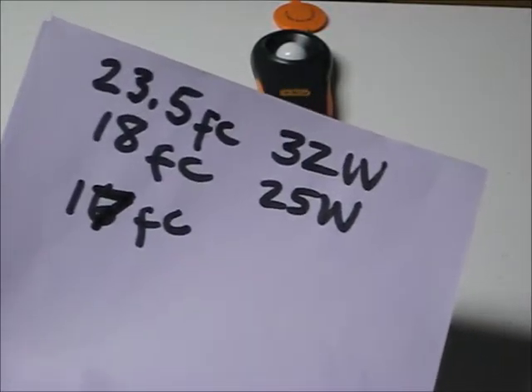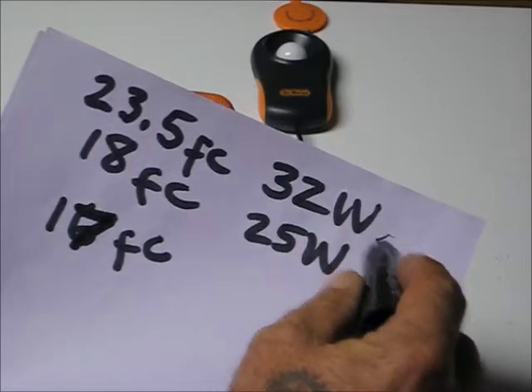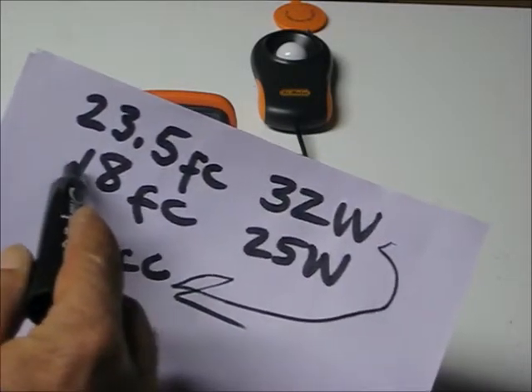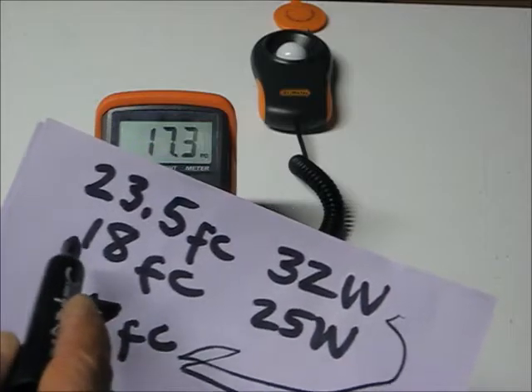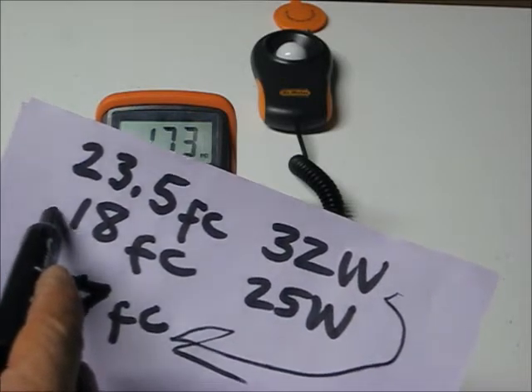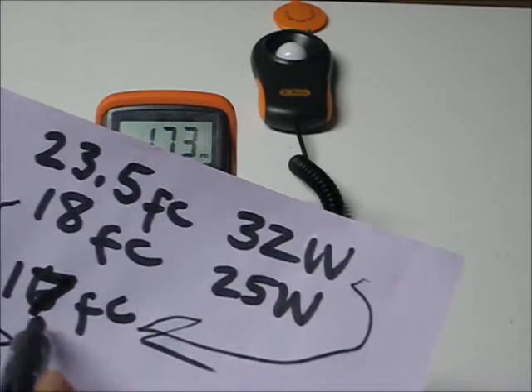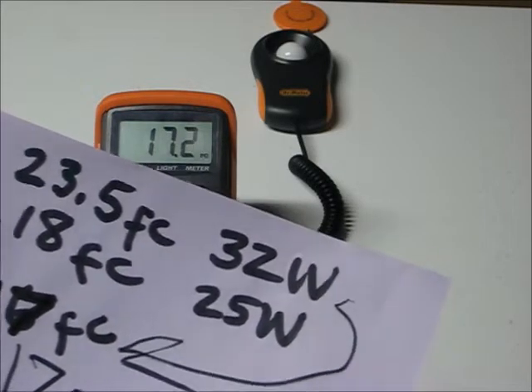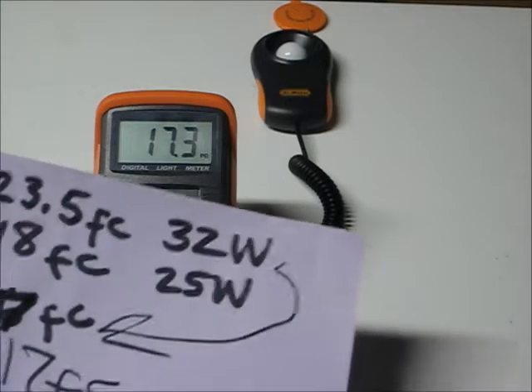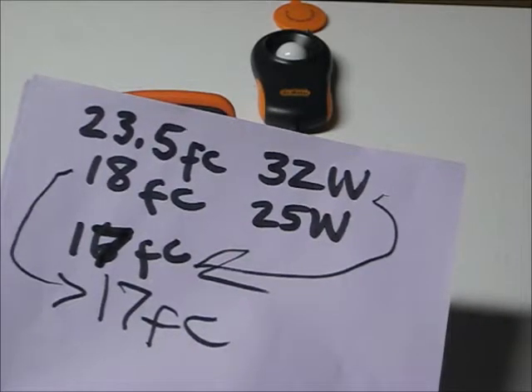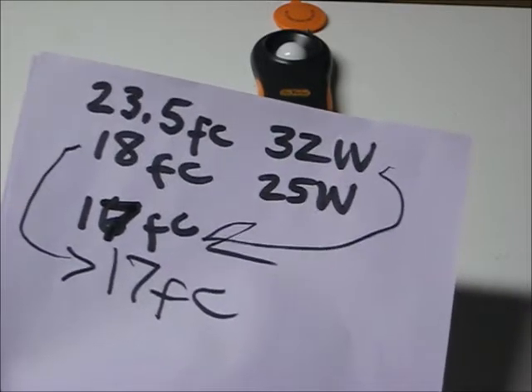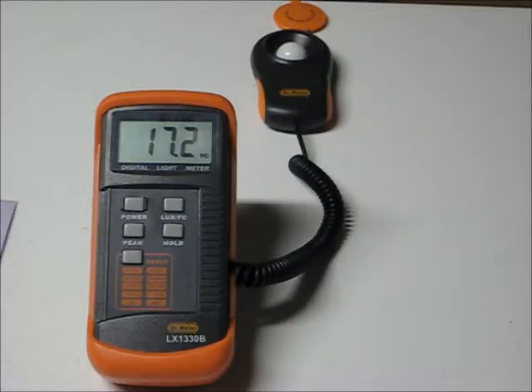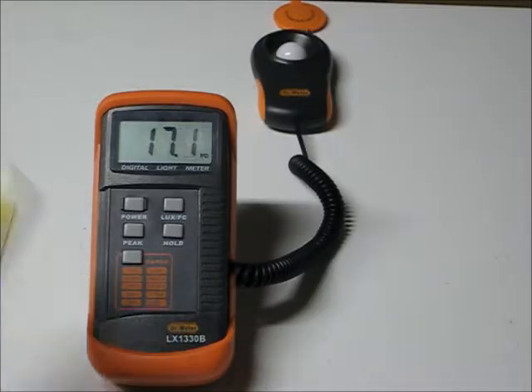Okay. We tuned those down there. The 25-watters could only put out 18. That's all you can get out of them. And when we reinstalled them, they went to 17 foot candles. So this shows you that you can do automatic lumen maintenance with a daylighting sensor, a closed loop daylighting sensor. And it should work just fine. And this would be a supply closet or an interior office or something like that.